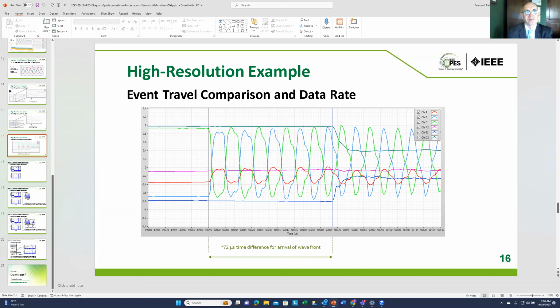So you do get a correlation of what were the very fast things happening around that event, most of which decay and die off within milliseconds, right? So they're not as relevant maybe 10 minutes later. And then again, slower waveform sampling, wider time range, and then PMUs or phasors wider, or continuous, but at least wider. That allows you to manage with priority the volume of data. You're right, the data can become very large, very fast if you were sampling at this rate and keeping everything.